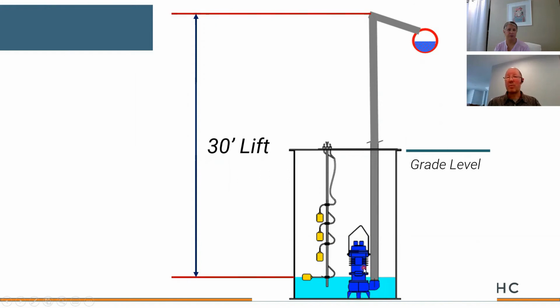Now, what's important with an open system? The pump is responsible for lifting water. In this case, we're assuming 30 feet of elevation from the bottom, our minimum water level in the basin, to the very top of our 90 or our bend in the piping before gravity feeds into city. We're assuming 30 foot of rise.